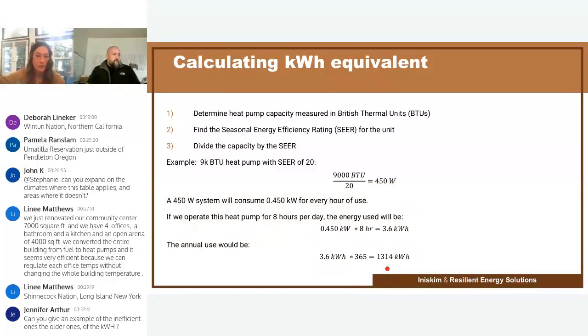Give an example of inefficient ones. If you have an older unit, you need to figure out the SEER rating on it, the energy efficiency rating. You should be able to Google that for a unit, or contact the manufacturer if you can't. Let's say, for example, it was 10 instead of 20 - that's a really extreme number. But if I divided by 10 instead, this would be using 900 watts instead of 450. So I'd take that 900 watts, turn it to 0.9, and multiply it by the 8 hours. That basically doubles the usage. So instead of 13, 14 kilowatt hours, it would be 2,600 kilowatt hours. Still a relatively low number in terms of energy usage, if you ask me.